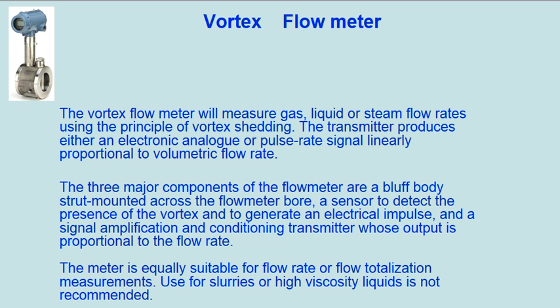The Vortex Flow Meter will measure gas, liquid, or steam flow rates using the principle of vortex shedding. The transmitter produces either an electronic analog or pulse rate signal linearly proportional to volumetric flow rate. The three major components are: a bluff body strut mounted across the flow meter bore, a sensor to detect the presence of the vortex and generate an electrical impulse, and a signal amplification and conditioning transmitter whose output is proportional to flow rate. The meter is equally suitable for flow rate or flow totalization measurements. Use for slurries or high viscosity liquids is not recommended.